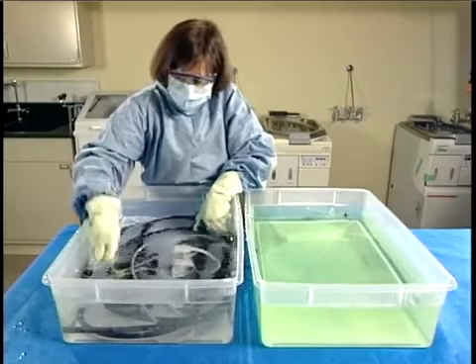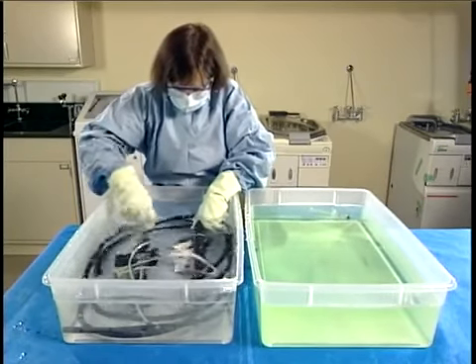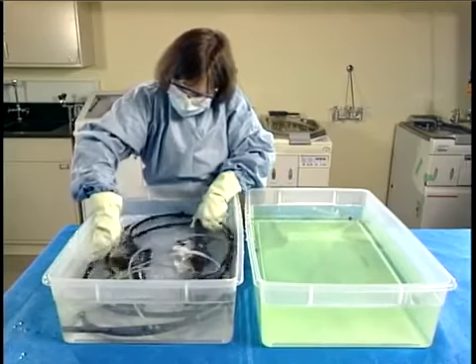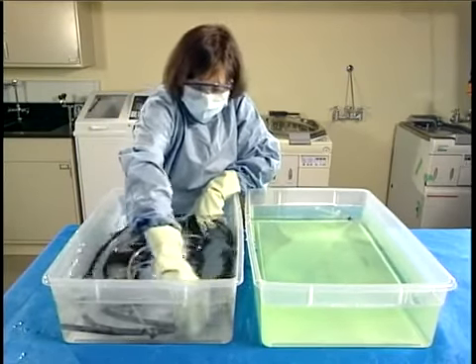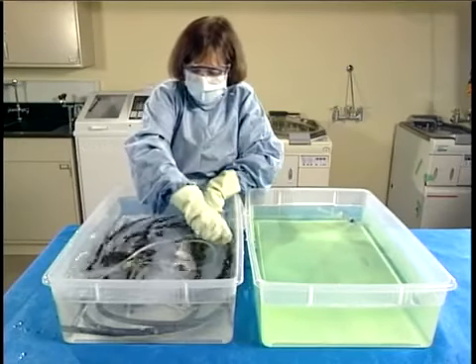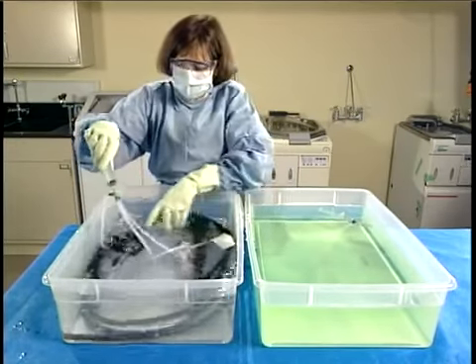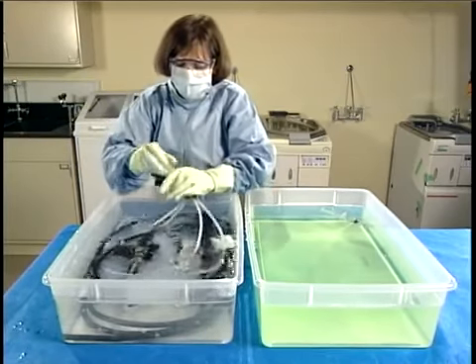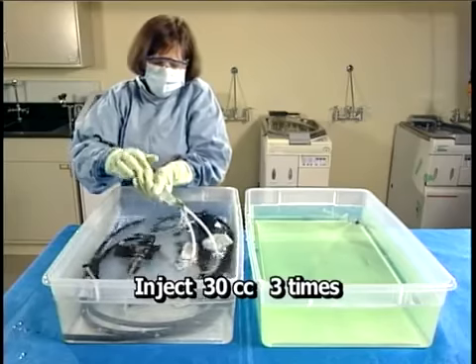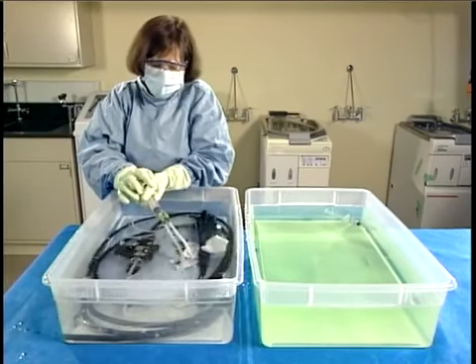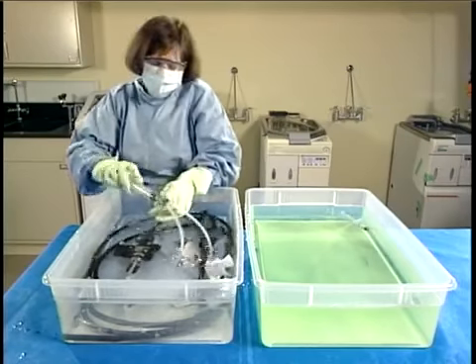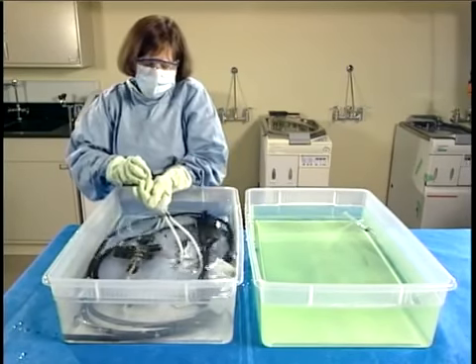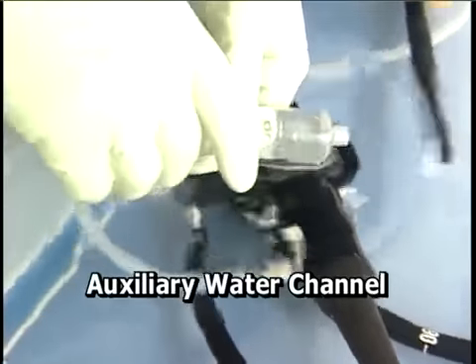With the instrument submerged, use a fresh, sterile, lint-free cloth to thoroughly wipe and rinse all external surfaces. Next, with the intake filter immersed in the rinse water, use the syringe to flush 90 cc's of rinse water through the air-water channels. Move the syringe to the suction connector and do the same to rinse the suction channel. If you are reprocessing an endoscope with a special channel, use a syringe to inject water into the auxiliary water channel.